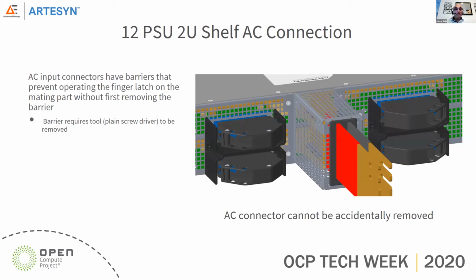Moving on, we'll talk about the shelf AC connection. As pointed out by Ming, you have the option of using either 2 AC input connectors or 4 input connectors. The AC connectors cannot be accidentally removed, because there's a protective covering on top that requires a flat screwdriver or tool to remove them. This is a good safety feature inherent in this power shelf.